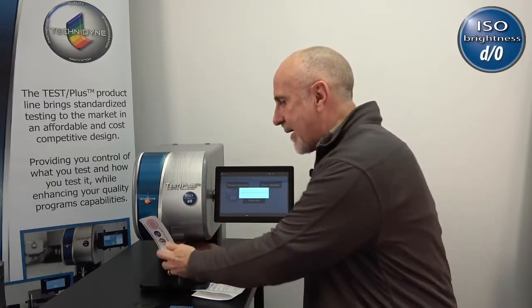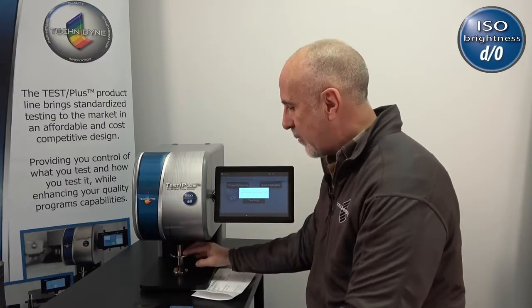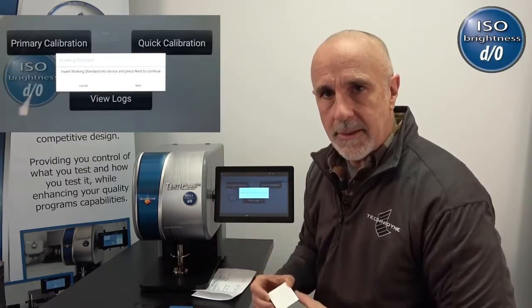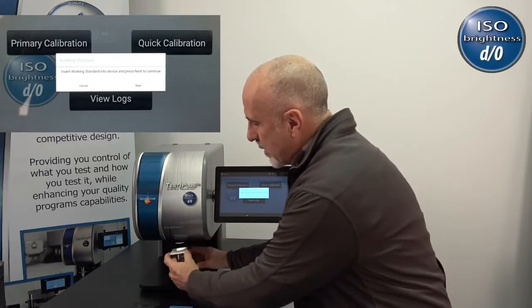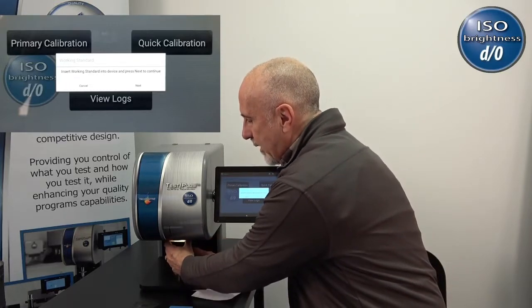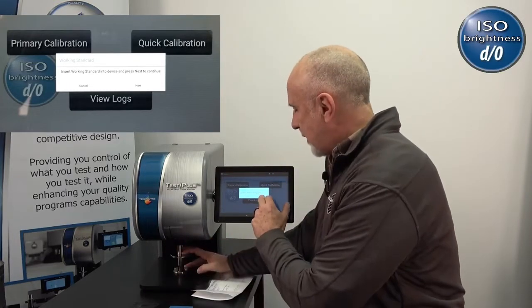Once that's completed, it will store that voltage level, so you won't need to worry about doing that again until the next primary calibration. Now the last step in the sequence is to evaluate the working standard. So the software says load the white working standard there and select OK.